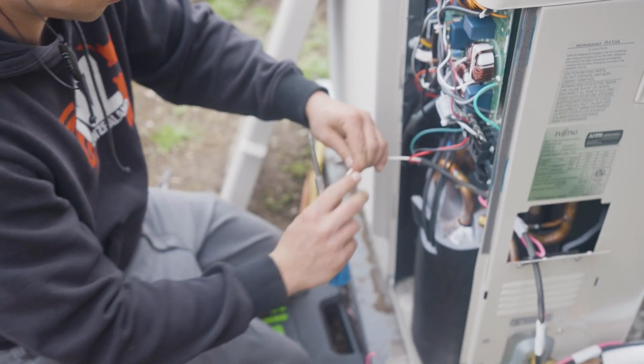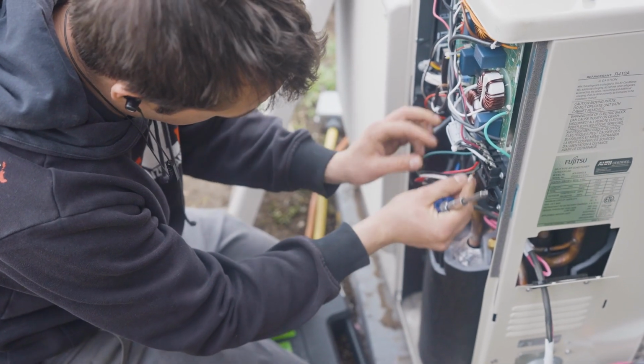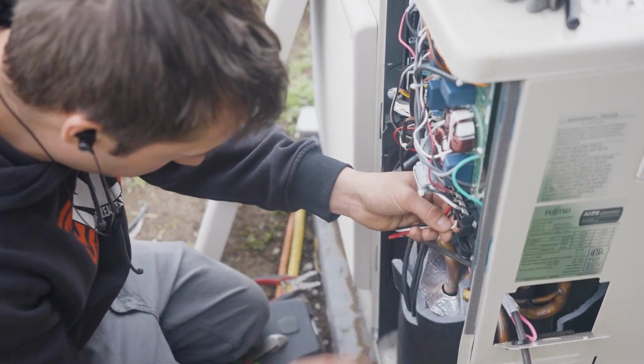Another thing for efficiency, from my understanding, is the compressor turning on and off. When that compressor bangs on, it uses an inrush, a large amperage number, which then converts to your wattage, which is your energy efficiency. Having that bang on and off all day long is higher wattage. These types of systems allow you to soft start, so it starts low and ramps up. You can dial in how fast that ramps up and ramps down. We can really dial in the temperature.